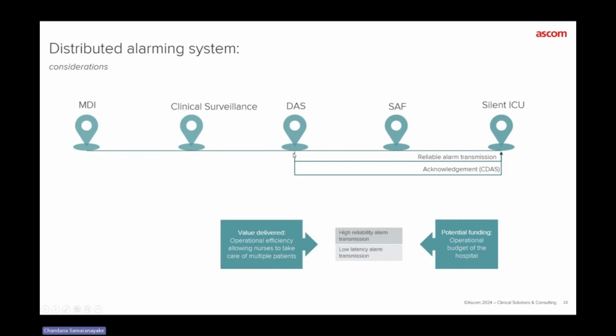That gives you the ability, in the future, to transfer alarms in less than 10 seconds to an alarm distribution system. A reliable alarm distribution system can look for breakages within the system, tracking each part of the chain — from bedside device to the system, from the system to the alert manager, from the alert manager to the mobile device. All of these parts are places where things can go wrong — somebody could pull out the cable from the device, and the connectivity stops.